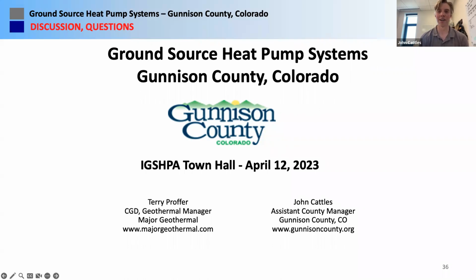That was not a condition that was planned for in any way, but it was good for us to watch that happen. That was on our courthouse, where we do have a backup boiler, and I intentionally did not use it. I wanted to understand how that system would perform without the backup, knowing I could flip a switch and inject heat into the system. I ran it without the backup boiler and pushed the limits, and the system recovered quite well. We never needed the backup boiler even in that condition. So yeah, the systems work really, really well.